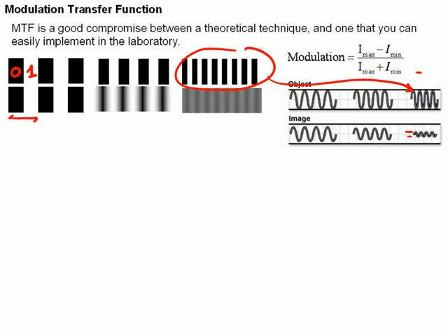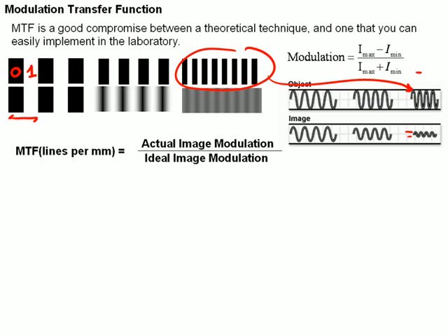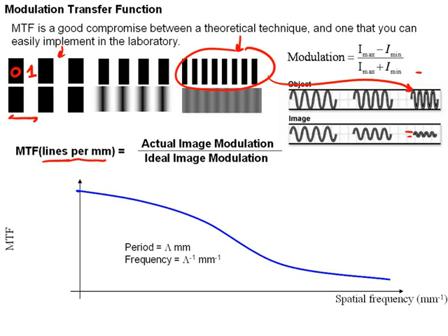You also notice that the modulation is a function of the spacing between the bars, and this leads us to the modulation transfer function, which is defined to be the actual image modulation divided by the ideal image modulation for a perfect imaging system, neglecting diffraction, as a function of lines per millimeter, where this has many lines per millimeter, and this has few lines per millimeter. So a modulation transfer function of a hypothetical system might look something like this. Notice that the vertical axis is the modulation transfer function, which will go from 0 to 1, and the horizontal axis is the spatial frequency. We define the period as the spacing between the bars in millimeters, and the frequency is simply the inverse of the period, in the same way we do it in the time domain.